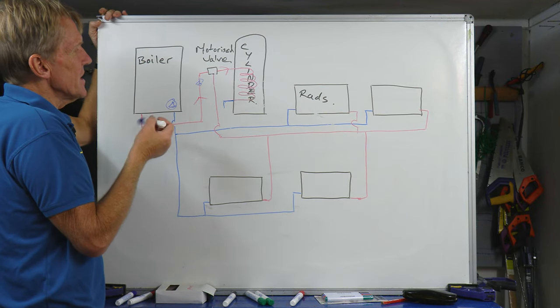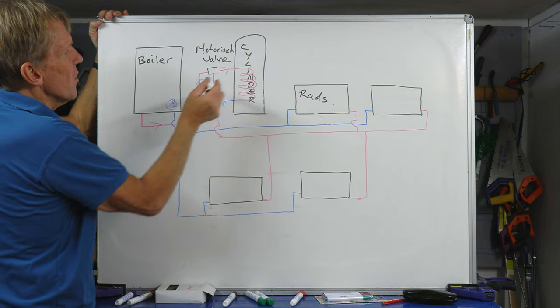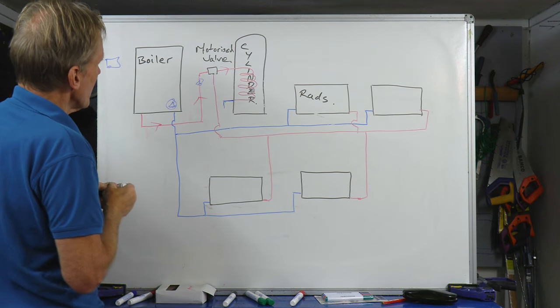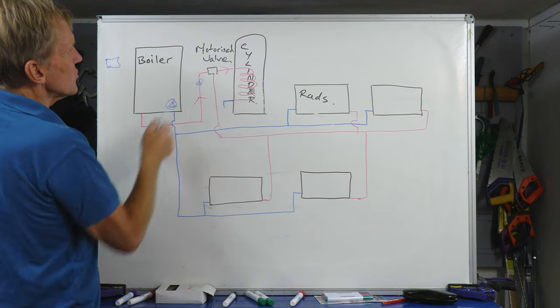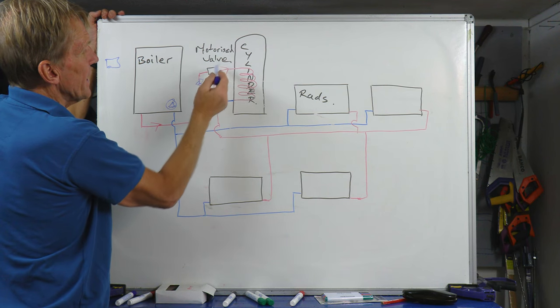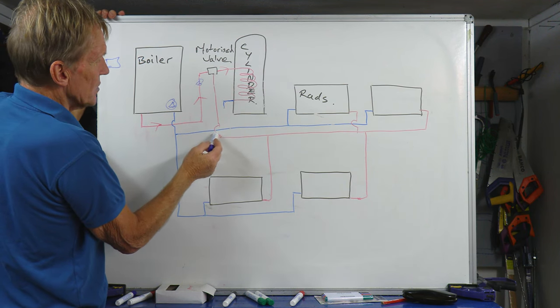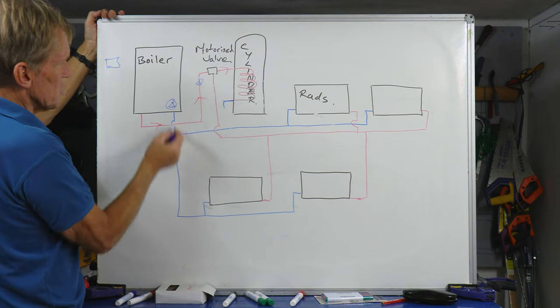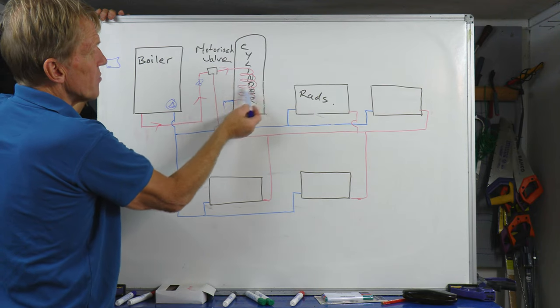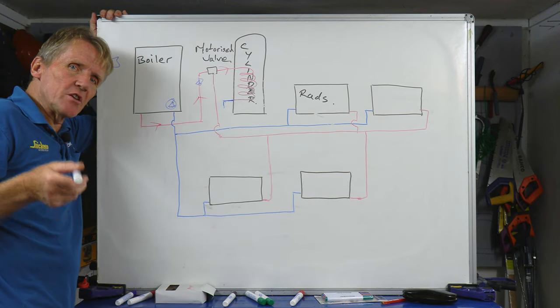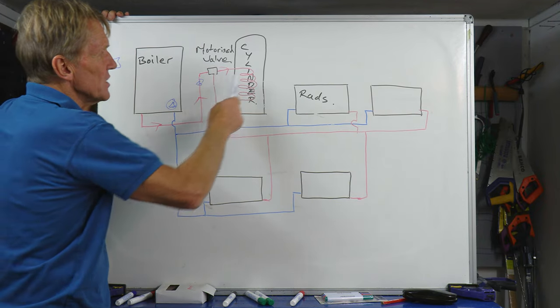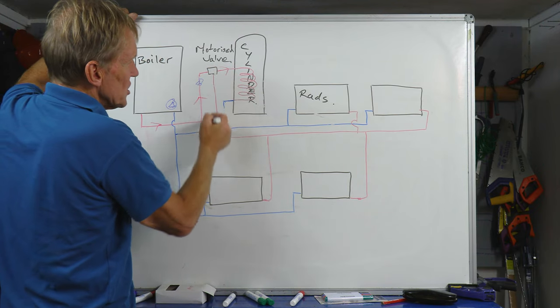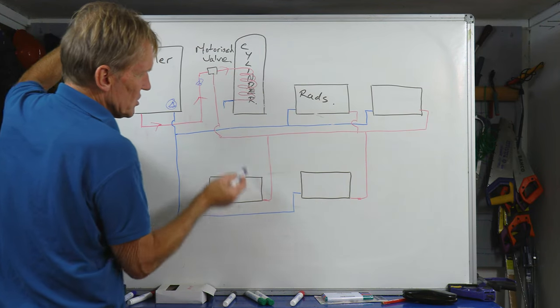So in the winter when you've got the cylinder calling for heat and you've got a room thermostat somewhere that is also calling for heat, it will tell the motorized valve to open up and it will allow water to go down into the radiators and circulate its way back to the boiler. It will also allow water to go through to the cylinder until the point where the cylinder is satisfied. In other words, it's reached its full temperature, nobody's having a bath, nobody's having a shower, so it will turn that circuit off and just leave the central heating running.